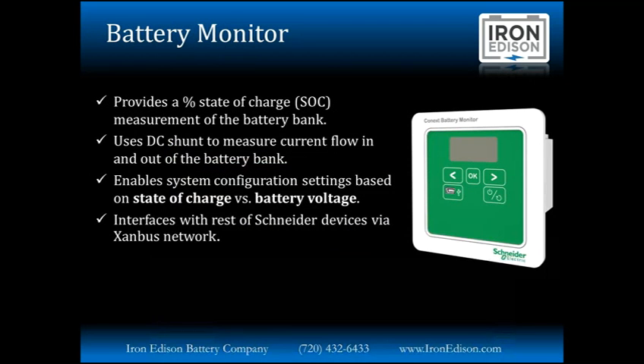Moving on, the next accessory we're going to look at is the battery monitor. What the battery monitor does is it provides a percent state of charge measurement of the battery bank. The way it does this, there's a DC shunt that's included with this. And instead of just measuring the battery voltage to get a rough idea of the state of charge, the shunt is going to measure current flow both in and out of the battery, basically counting current or amps going in and out of the battery to give you an exact percentage state of charge.